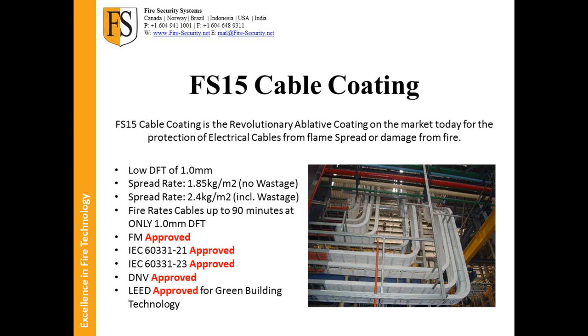Yeah. Okay. For instance, one of our competitors, who I won't mention, has an expandable polyurethane PU foam that's fire rated or fire stopping, like a 2 or 3 hour fire rating. It stops a fire dead in its tracks. There's no issues about that. But the off gas coming when it's burning is extremely toxic. Wow. So it's important for us to let everyone know that regardless of what form the FS15 takes, whether it's wet, dry, or fully cured, or under fire, there's zero toxicity to it. Okay.